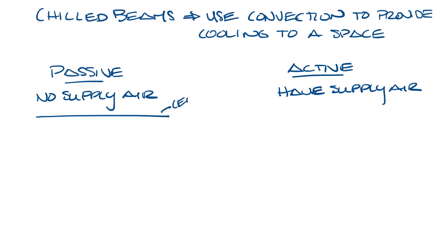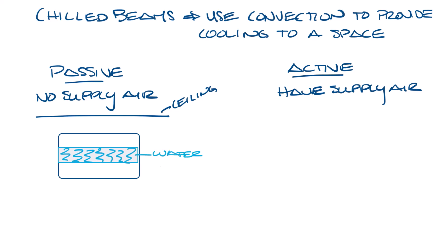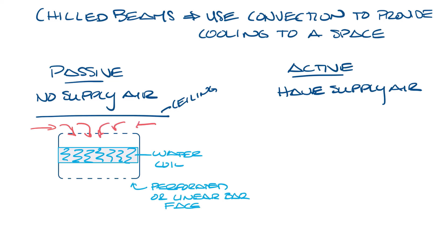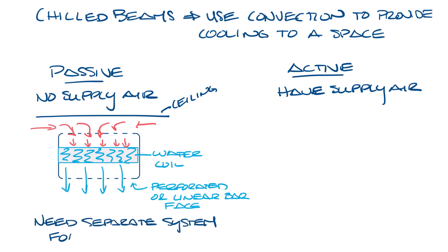Passive chilled beams will be mounted under a ceiling. You've got the casing and inside you have a water coil. And then there are openings on the top and the bottom. So the face of it is either perforated or linear bar grills. So as warm air rises from the room, it passes over the chilled beam and cools down and falls back into the space providing cooling. As I said, there's no supply air inlet on the passive chilled beam. So you have to supply a separate system for ventilation air to meet your ASHRAE 62.1 requirements.